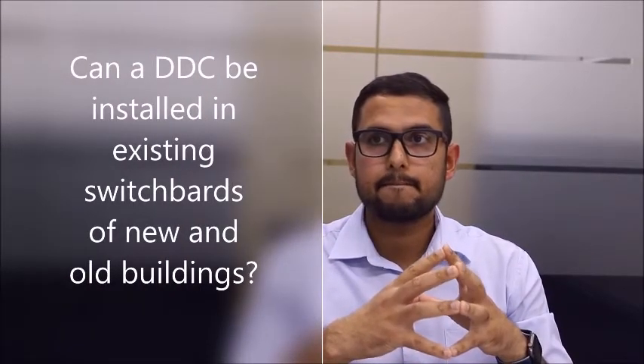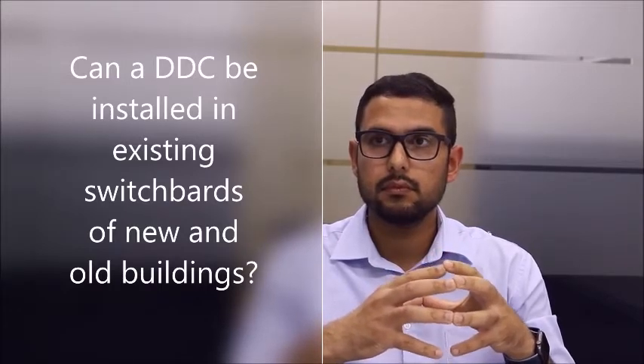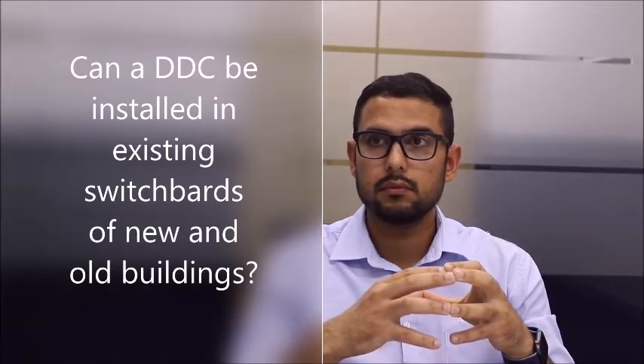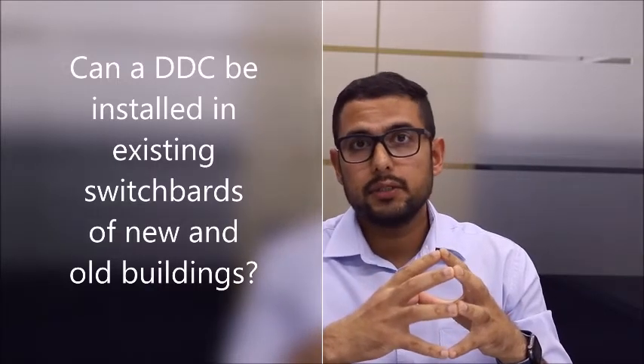If we have analog controls in a switchboard and we want to replace them, can the direct digital controller be installed in existing switchboards? Yes, it can do it. The direct digital control, which is often called a building management system, works on 2 to 3 different voltages. For binary inputs and outputs, it deals with 24 volt AC or 24 volt DC, depending on which relay type we use. And then it also works on analog signals, which as standard are 0 to 10 volt DC or 4 to 20 milliamp signals. So depending on what type of signal we are using and what sort of output we would need to interpret, it can replace those boards.